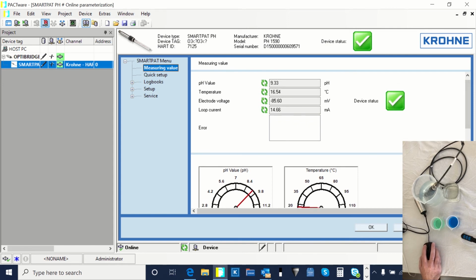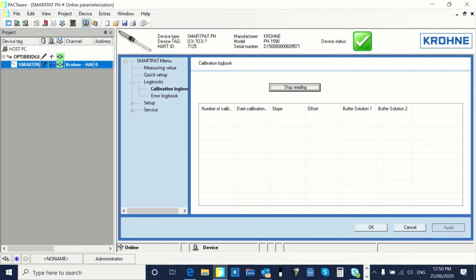What I'll do first is store to device. That'll load that calibration detail into the transmitter, and then if we have a look in a few seconds, we'll be able to go into the logbook, and that calibration will be logged inside the probe, and each calibration will be stored in that probe. So we'll come down here and we'll come to calibration logbook. We'll read the logbook, and we can see here 25th of the 6th, 2020, which is today, and we can see the buffers that we used, what the offset and what the slope was. And there's an earlier one, so you can see it's quite a long time since its last calibration.